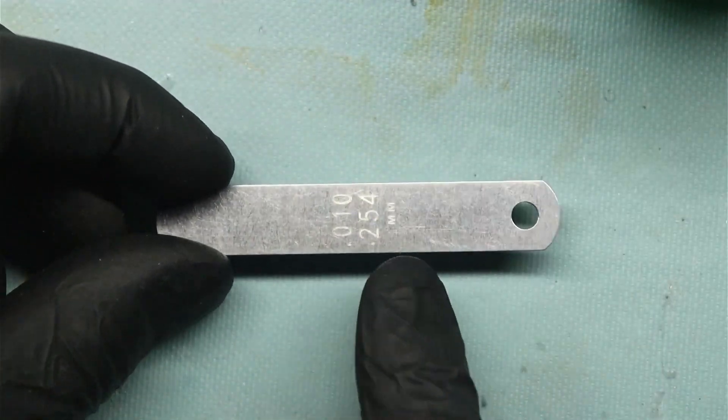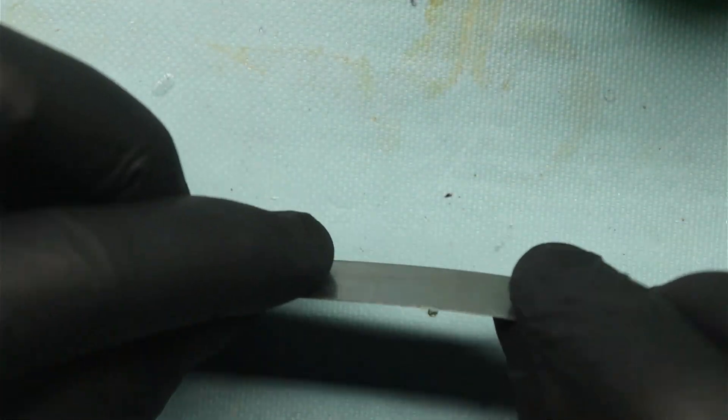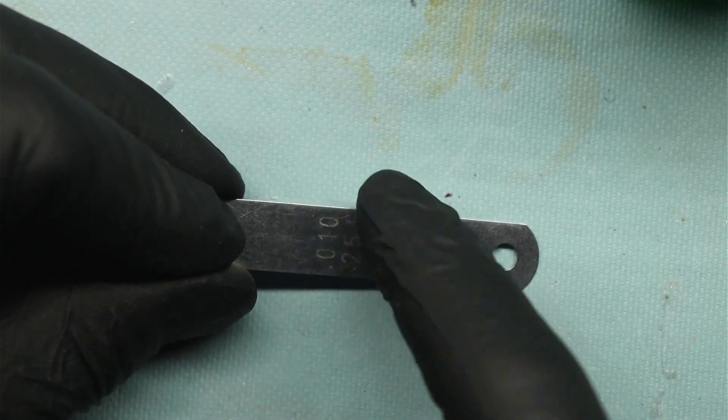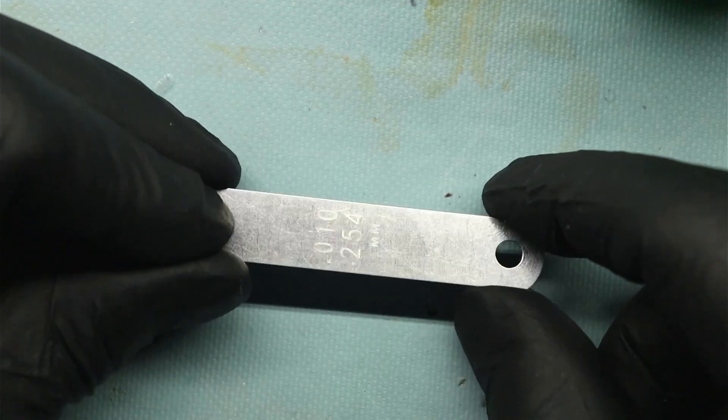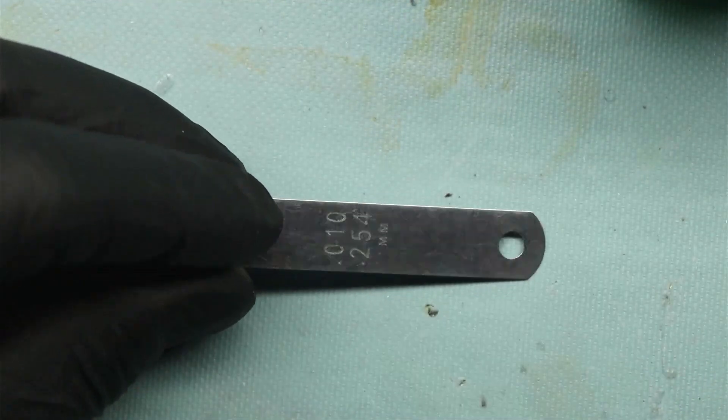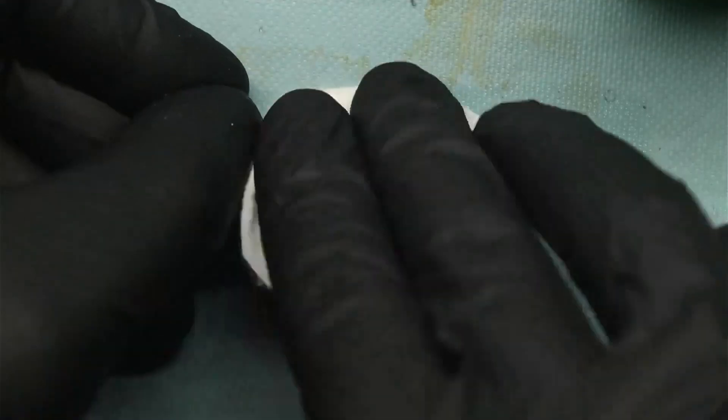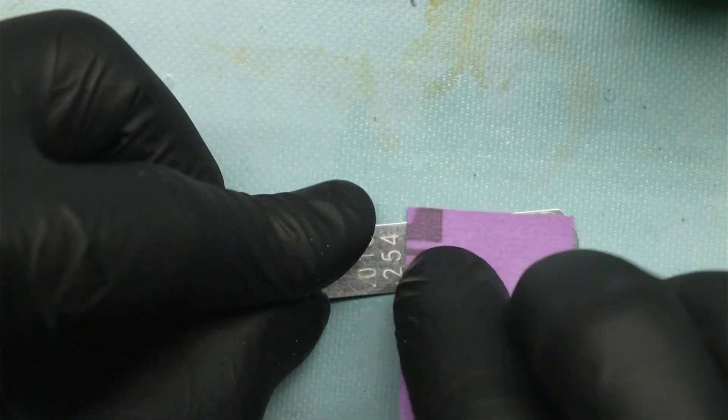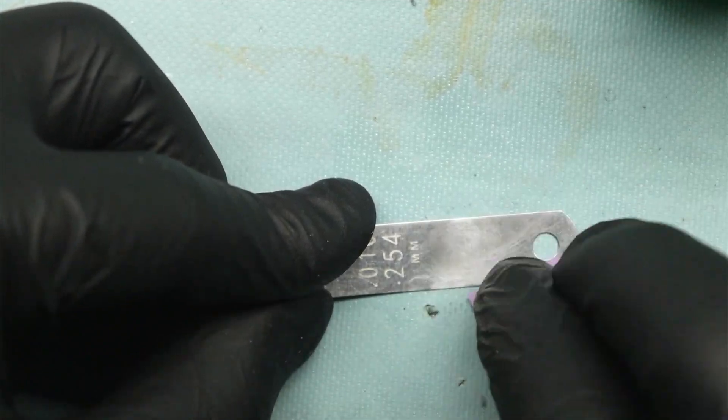Now we need to set up our surface to mount those guys too. So what I'm going to do is most of the bending is going to occur in this portion here once I clamp this down. So I do have some overlap on these letters. Normally you wouldn't want that. You'd kind of mark out with a number two pencil where you want to do it and then just wipe it off. And that kind of burnishes a line in it, which you can still see, but it does not affect the metal. You don't want to gouge it because your strain gauge isn't going to sit properly and flat on the surface. So anyway, I'm going to go ahead and start sanding this. Well, actually let's wipe it down first. So I'm just going to get both sides. Then we're going to sand it. So we're just going to go in little circles, small circles, and we're just roughing up the surface really.